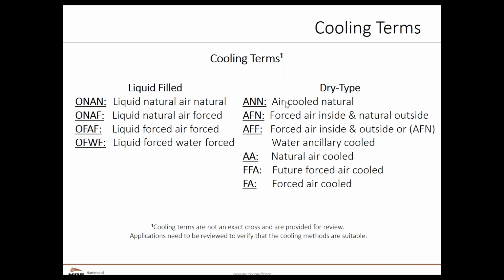There are different terms. Liquid filled has ONAN, ONAF, OFAF, ODAF, OFWF. Those aren't directly attributable to the terminology that we use for dry type transformers. So, if we see an ONAN, we don't necessarily have a direct equivalent. I guess the closest one for us would probably be AN, but again, different terms, and in some cases different methods to do the cooling. I'm not going to go into all of these, but just be aware when we see these cooling terms that start with an O on the left-hand side of this chart, we know pretty much that this was a liquid-filled specification.